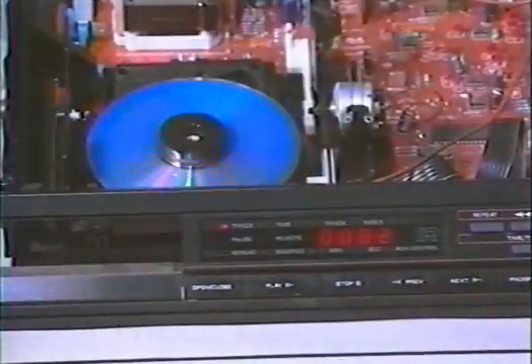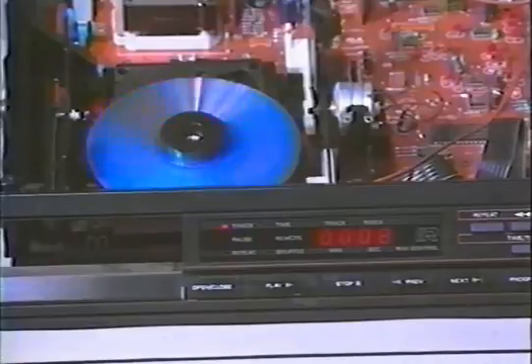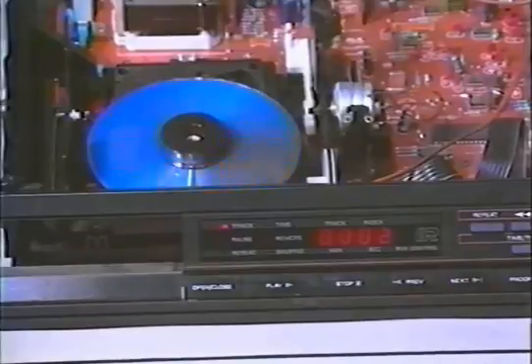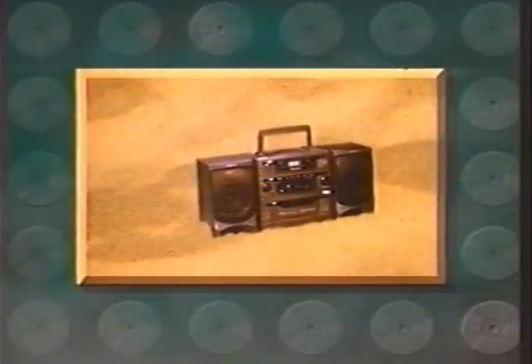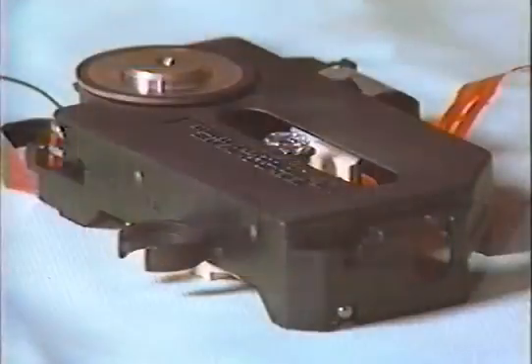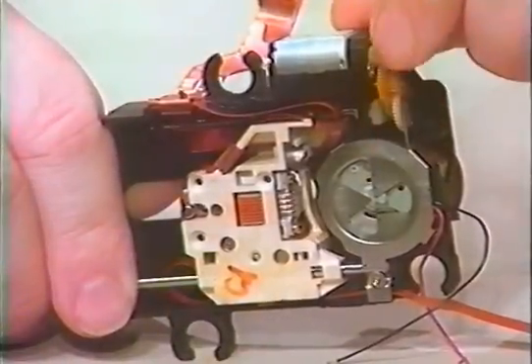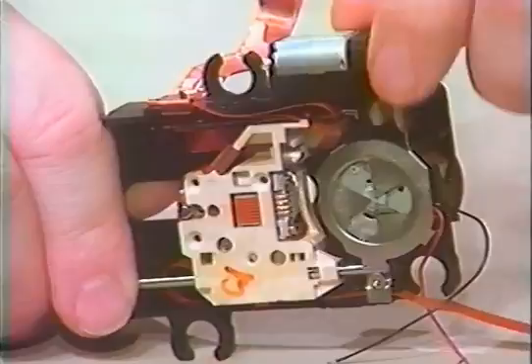Close inspection of the tracking may reveal a mechanical fault. Placing the unit in the tracking servo test mode may be helpful in locating a mechanical problem. This is especially true in the case of portable units that are likely to be exposed to adverse conditions, such as at the beach. Sand may get into the gears and sled mechanism, causing tracking error conditions. Clean and lubricate the mechanical section as indicated by the service manual for the unit being serviced. Also, carefully moving the tracking mechanism manually may reveal a mechanical fault.